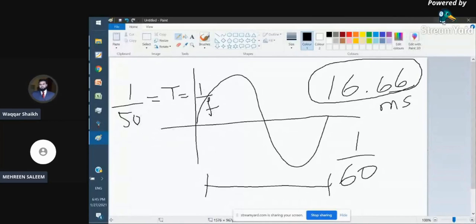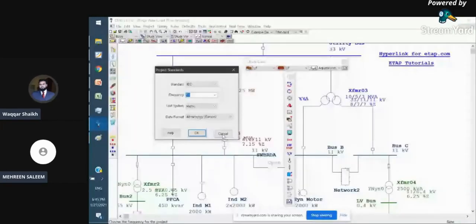Some protection relay manufacturers, whenever they give the time dial settings, or the settings for short circuit clearance, the instantaneous feature of the protection relays, ask for them in the form of cycles. So if we are using a 60 hertz system, we will be giving wrong input if the actual network is 50 hertz. This is a very important point, especially for those users who are using ETAP for protection coordination studies: always make sure that you are selecting the right frequency, because it will affect the duration to clear the fault depending upon your selection.